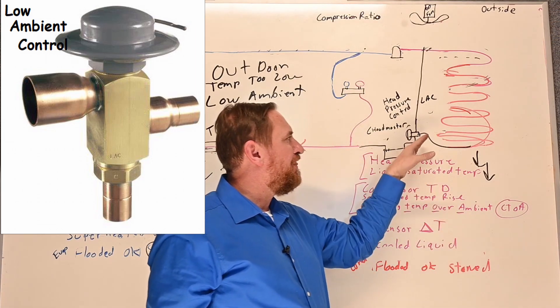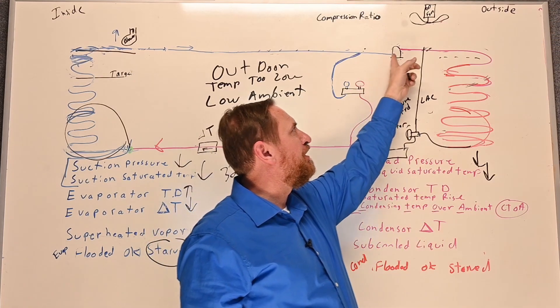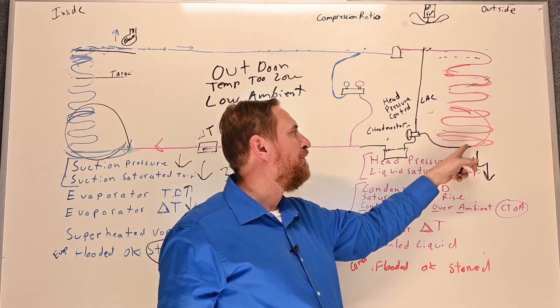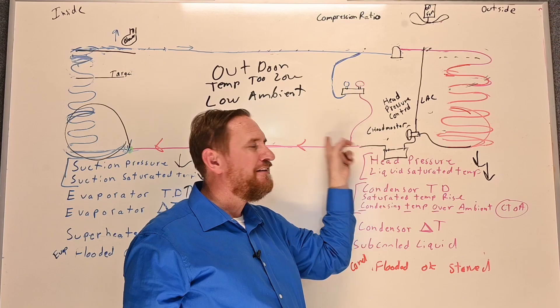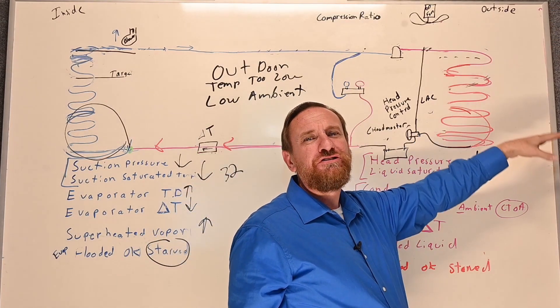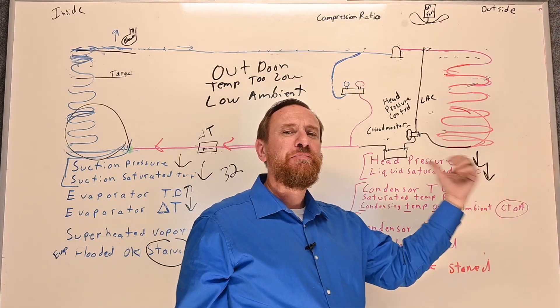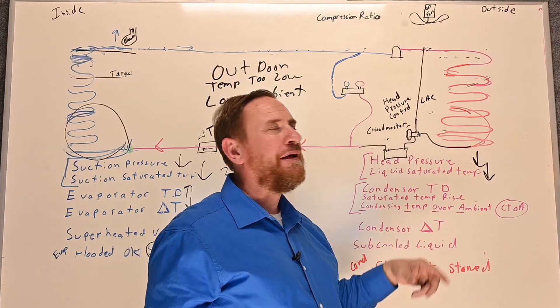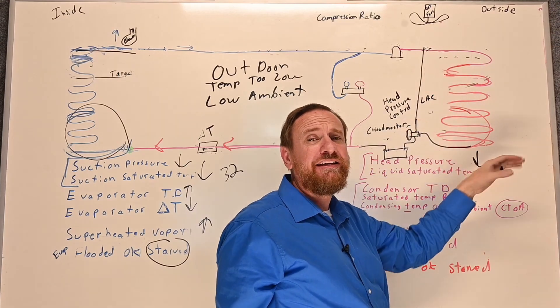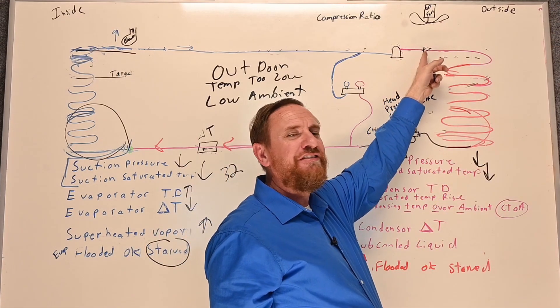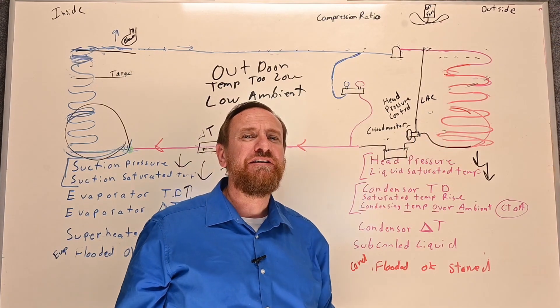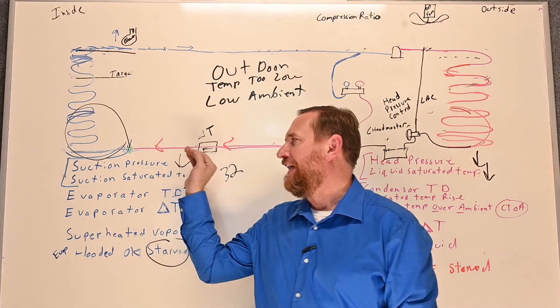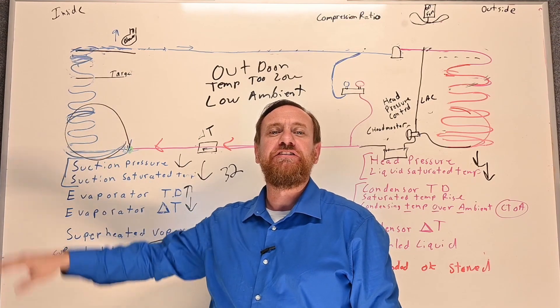So if we think about how this works with it, not in operation, the refrigerant goes past it. It's like it's not even there. It goes to the condensing unit. We de-superheat, we change from a vapor to liquid, we sub-cool. We go through our head pressure control like it's not even there and continues on through our system. As our outdoor temperature starts to drop down, we end up with lower and lower pressure, not enough pressure to push that liquid out. So what we actually do is this device takes over. What it does is then it starts to open. And what it does is it gives a path to bypass the condensing unit altogether. So it lets refrigerant come out of the discharge line and it pushes into the liquid receiver. Because that liquid receiver is holding liquid refrigerant, it's allowing that liquid refrigerant to be pushed out. And we have plenty of liquid refrigerant hitting our evaporator coil and our metering device. So that's really important.